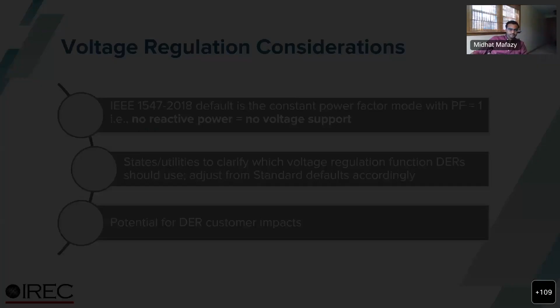The default setting for 1547-2018 is unity power factor, no reactive power from DER, meaning products will come off the shelf to provide no voltage support. So states and utilities will need to consider whether or not to turn voltage regulation on by default and which functions to use. Also, some functions are mutually exclusive, meaning only one can be turned on at a time. And some functions have the potential to impact customer finances. So you may want to address that when adapting the standard. We intend to spend more time on this in the future training. Next slide.